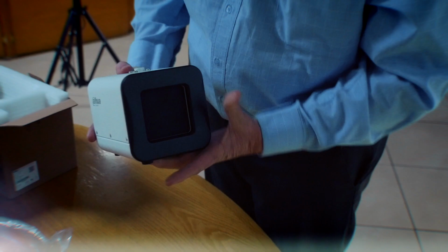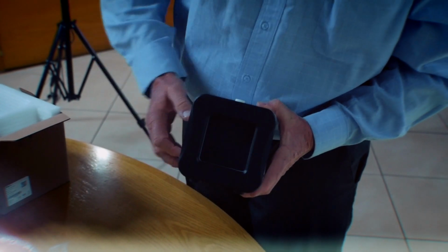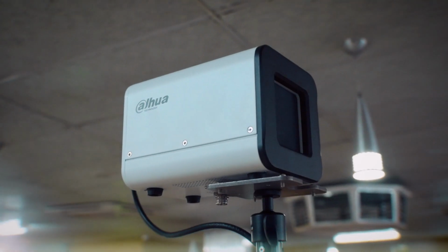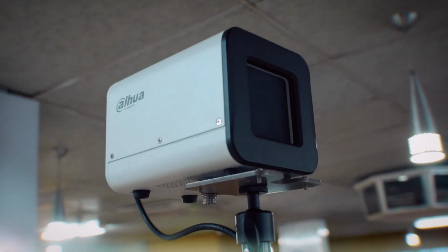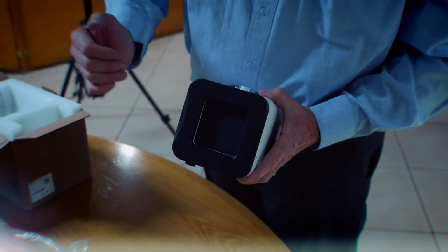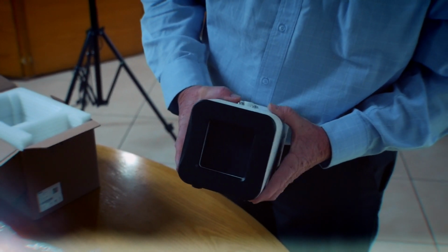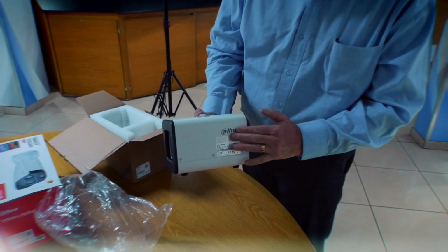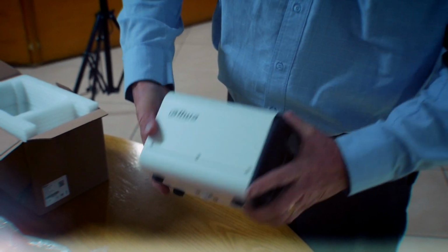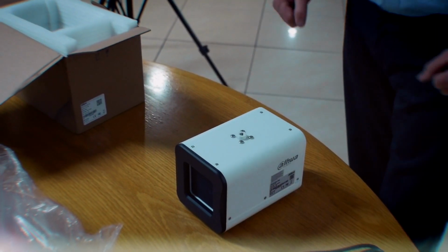It then emits that temperature as an infrared signal out of the device over here, which goes into the thermal camera. In the thermal camera we set it, telling it that the preset is 35 degrees, so that is 35 degrees, but that's what it feels like. The camera calibrates itself and then creates an accuracy of 0.1 of a degree. A vital part of the system from Dahua, the suppliers and manufacturers of this device. A critical part of the entire solution.